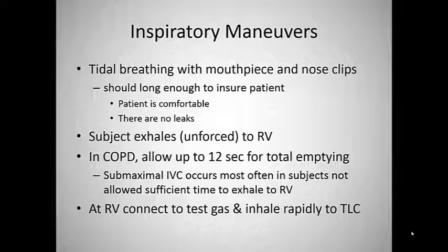Again, this is where we fall down a lot. I see the tech telling somebody, oh, blow, blow, blow. They blow out, out, out, out. You see the thing kind of curve down at the bottom? Take a deep breath in. As long as you can actually see on the machines when a patient's achieved zero airflow, you make that patient keep pushing until he gets there, and it can be up to 12 seconds. Again, this is one of the biggest errors we see when we get rushed diffusion efforts. Submaximal IVC occurs more often in subjects not allowed sufficient time to exhale to RV. That's the biggie. And then when a patient gets to residual volume, you connect them to the test gas and you inhale rapidly to TLC.